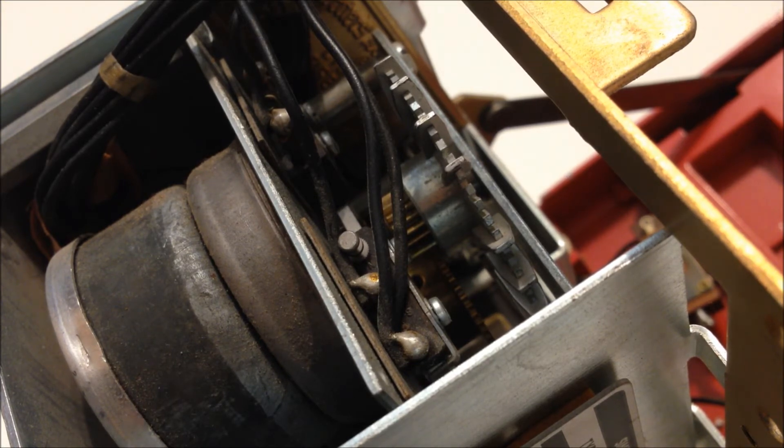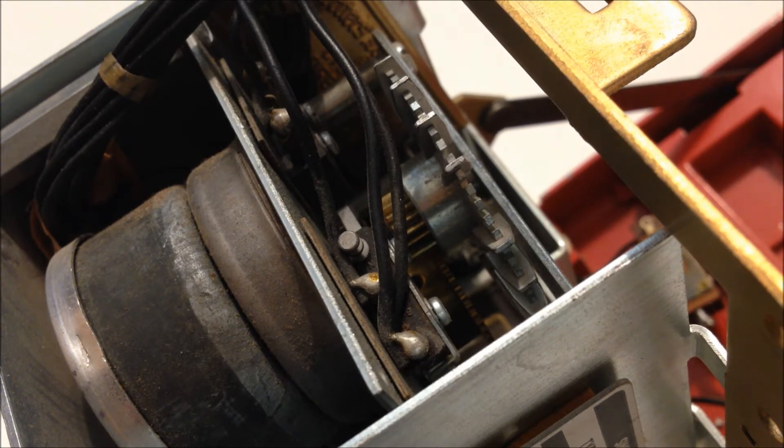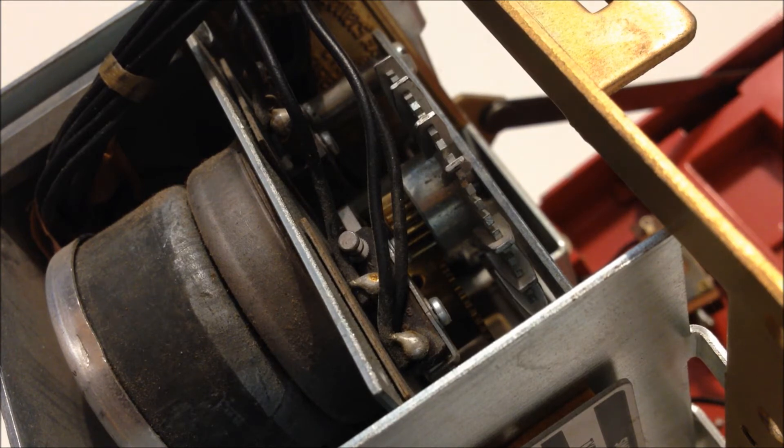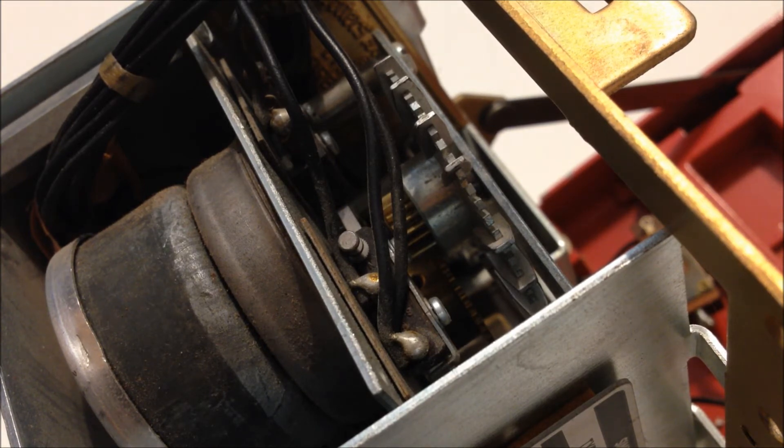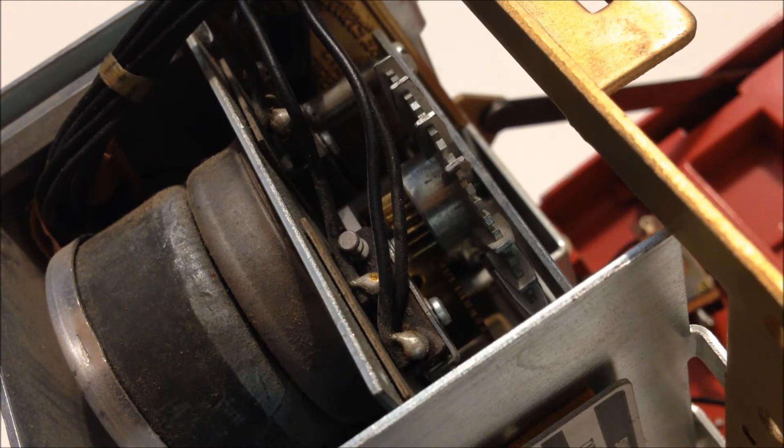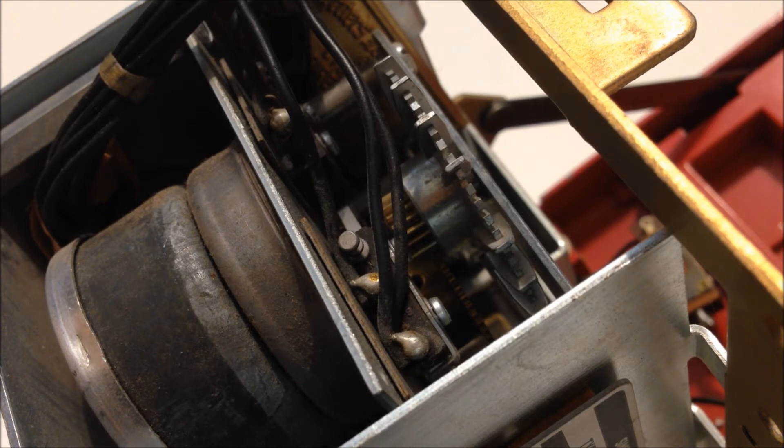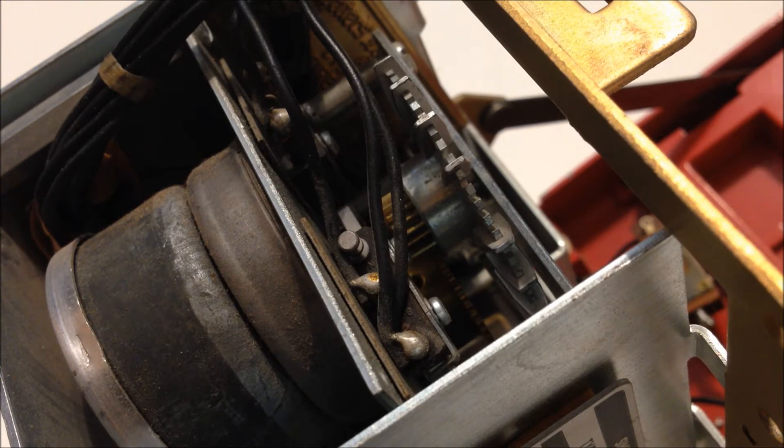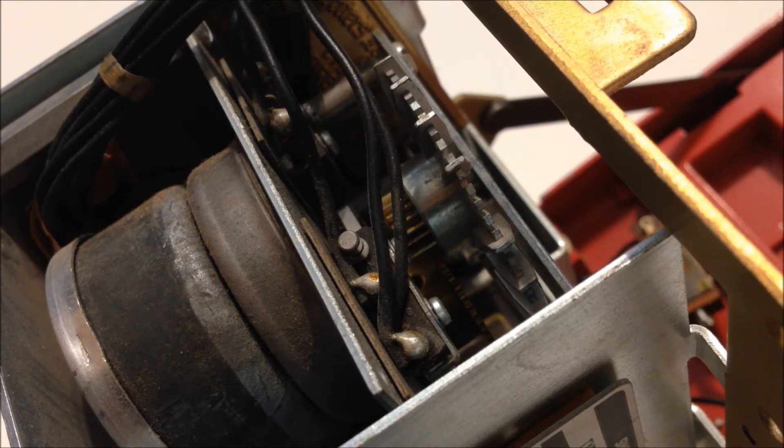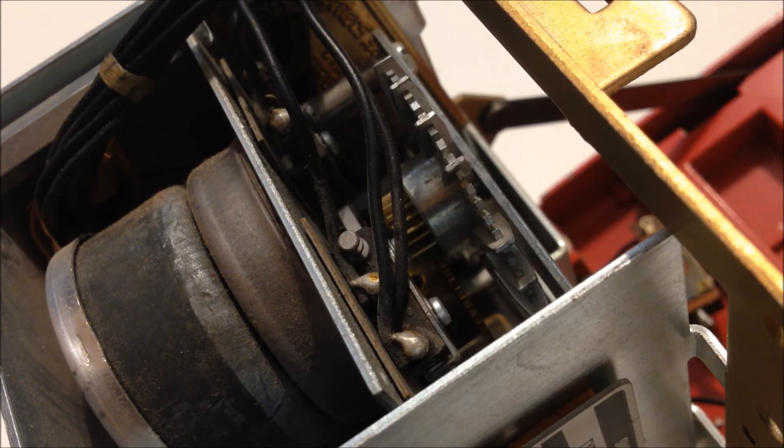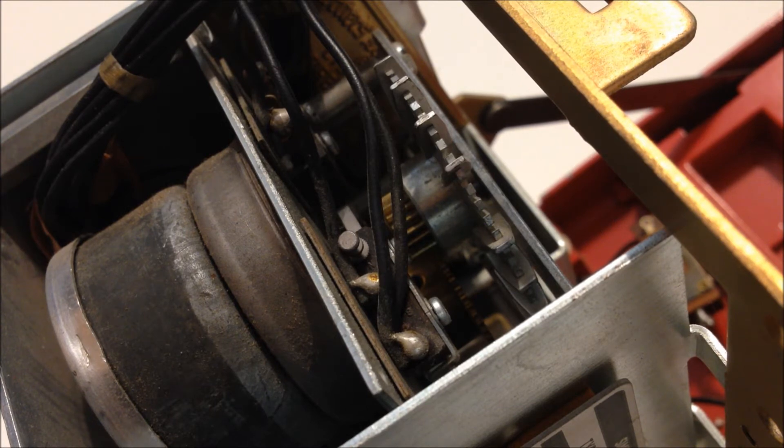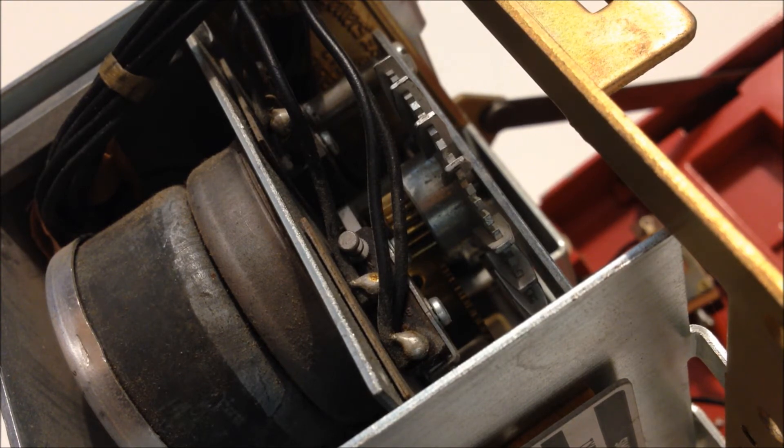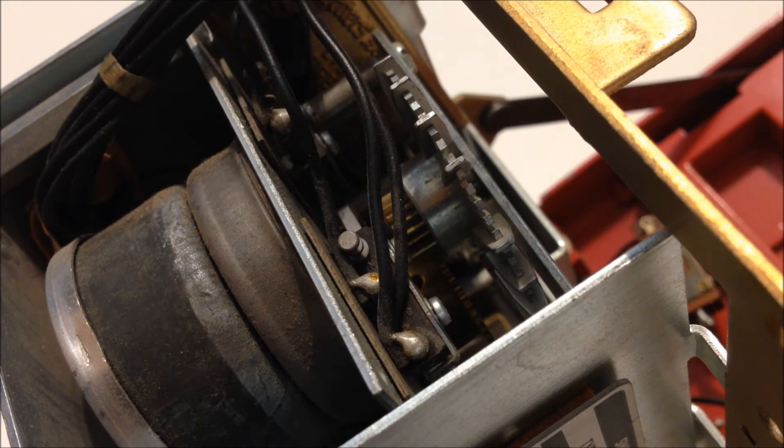So basically this wheel has an indentation on it that its starting position is up by these micro switches. When the motor is activated that wheel will turn with the whole assembly, and as the code wheel does four rounds of code that metal wheel will rotate back around to its position. The micro switches are constantly tracking the location of this wheel. They have little rollers on the levers so they can follow it around tracking the position of the wheel. And when that wheel returns back to its initial position, meaning that the coding wheel has done four rounds of code, that will trigger one of the micro switches and it will cut the motor. So that's how we're able to get the four rounds of code even though it's electrically driven.